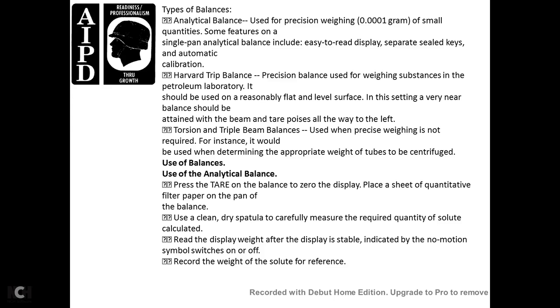The trip balance and precision balance used in the petroleum laboratory should be placed on a flat and level surface. The zero net balance should be attained with the beam and tare poise all the way to the left. The triple beam balance is used when precise weighing is not required — for example, to determine the appropriate weight of tubes for centrifuge. To use the analytical balance: zero the display; place a sheet of filter paper on the pan; use a clean dry spatula to carefully measure the required quantity; read the display when stable indicating no motion; record the weight for reference.